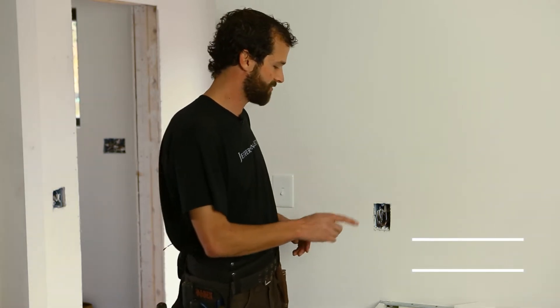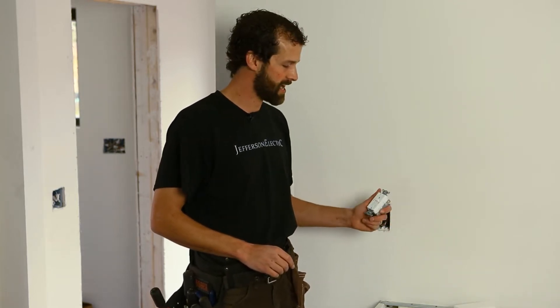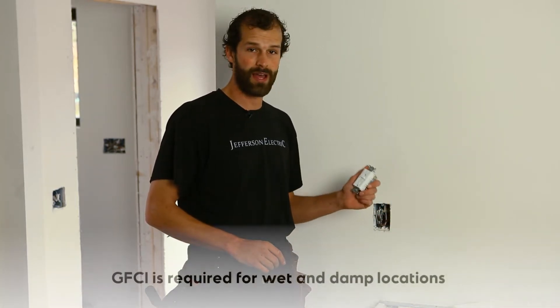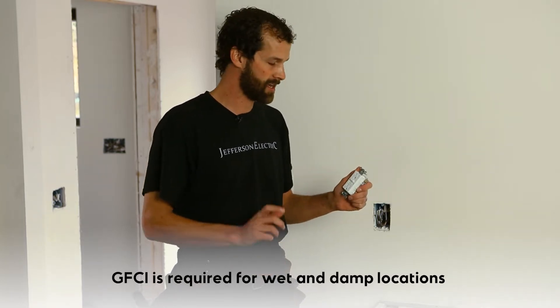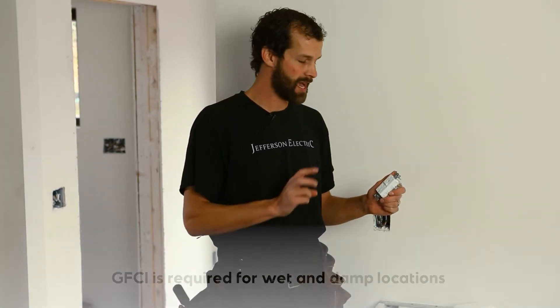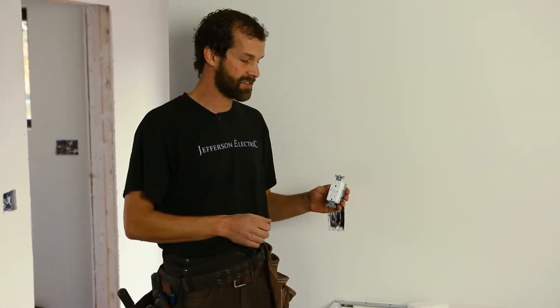Now here we start the outlets that are serving our kitchen countertop. The first outlet we have is a GFCI receptacle. GFCI is a code requirement for wet and damp locations. It monitors the difference between hot and neutral, and if there's a current imbalance more than five milliamps, this device will trip at the device. You'll see a test and a reset button. It'll trip at the device to cut power to anything that's plugged into it for safety purposes.